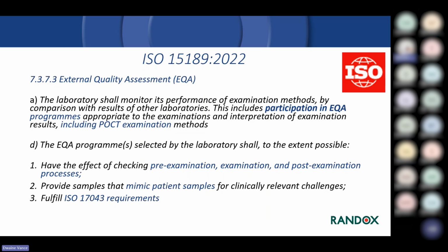The lab shall monitor its performance of examination methods by comparison with results of other laboratories. This includes participating in an EQA program appropriate to the examination and interpretation of examination results. The EQA programs selected by the lab shall, to the extent possible, have the effect of checking the pre-examination, examination and post-examination processes, also referred to as pre-analytical, analytical and post-analytical processes, and provide samples that mimic the patient sample for clinically relevant challenges.